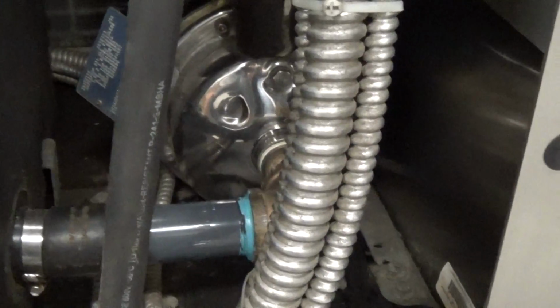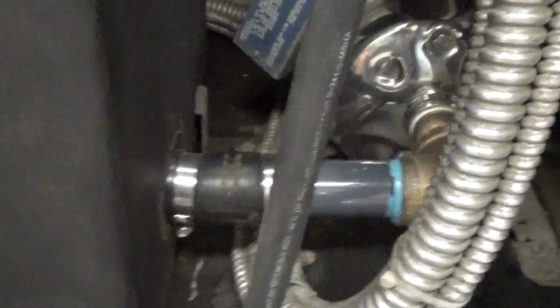I'm going to go around the unit first with the covers off. This particular unit, you need to have the covers on to get proper airflow through the condenser. On the inside of the unit here we have our insulated reservoir tank. Now this unit here, we modified the plumbing for a brewery application. What that means is we have our 2 horsepower stainless process pump, and that is set up to draw off the tank, okay? Then it discharges up, and in this case back into the tank where the heat exchanger is. So we're actually pumping the fluid directly into the heat exchanger before it goes out to the process.